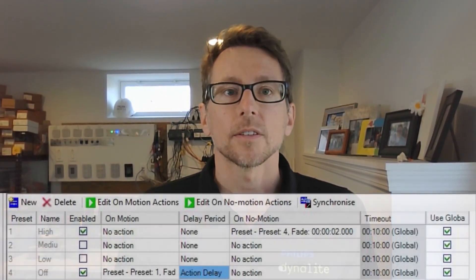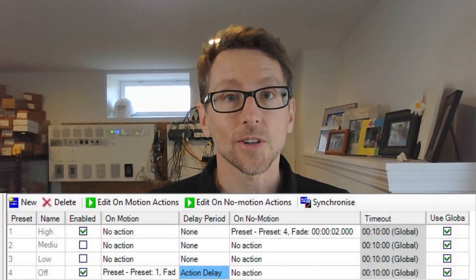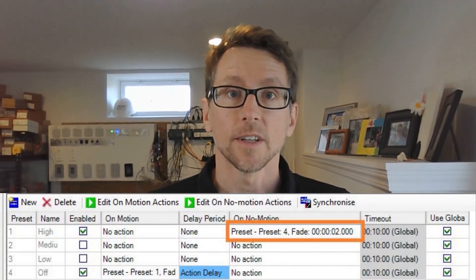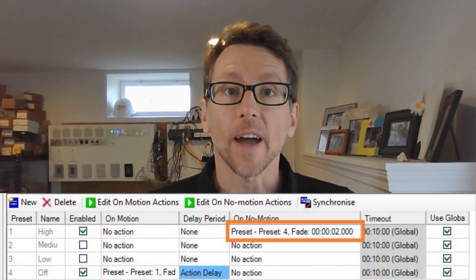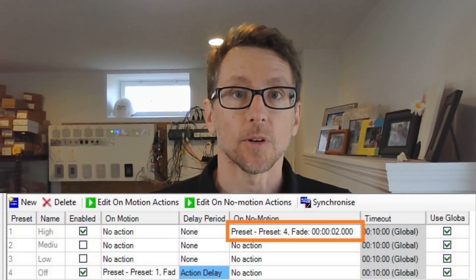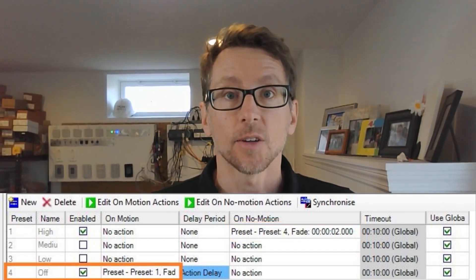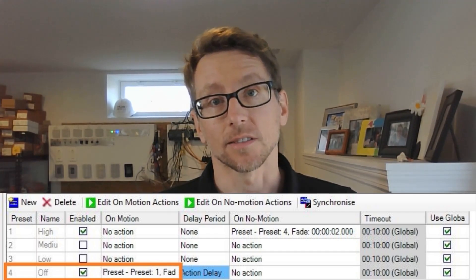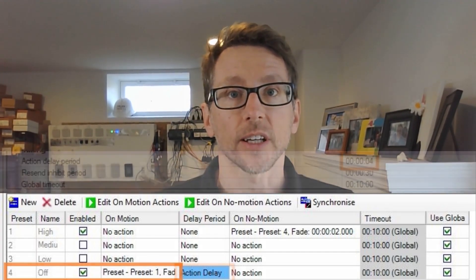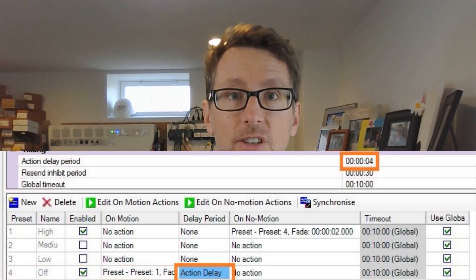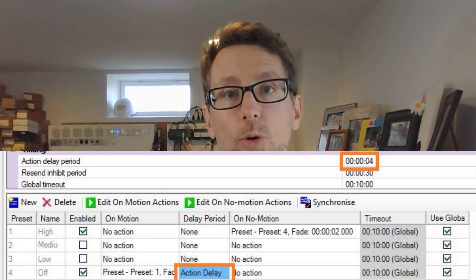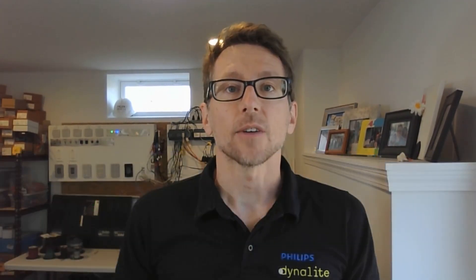Next up would be a simple occupancy sensor, like something you'd find in a closet that doesn't have a switch. You can see here that we still turn the lights off in preset one, but now we've added a few more rows to the motion table. If we see motion in preset four — the off preset — we turn the lights on. If the room has a switch in it, we'll need to put an action delay so that you have time to leave the room after turning the lights off.